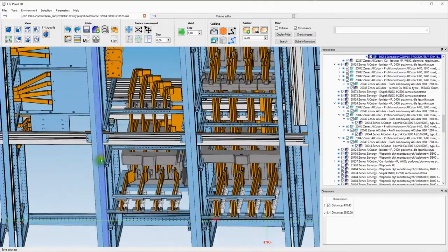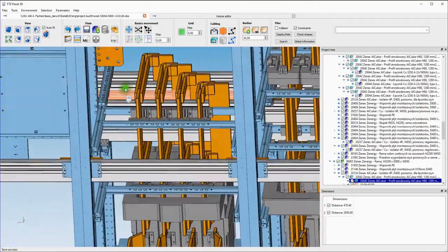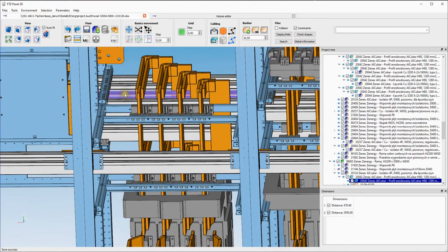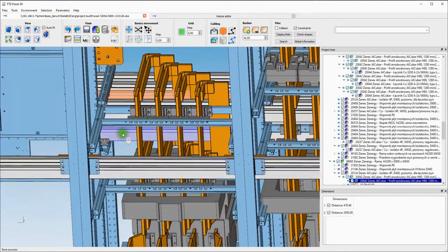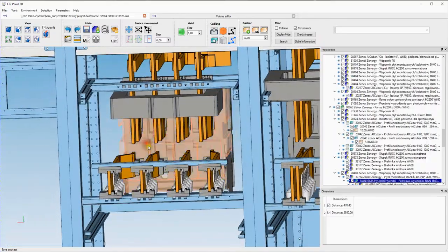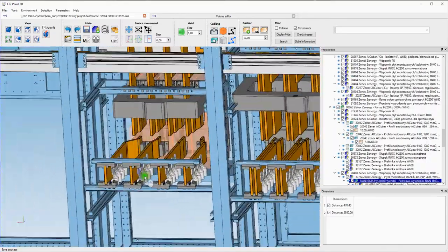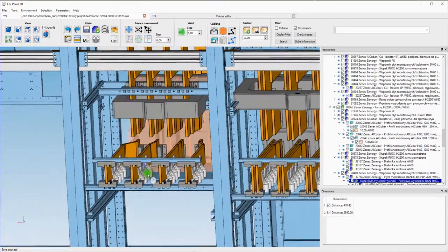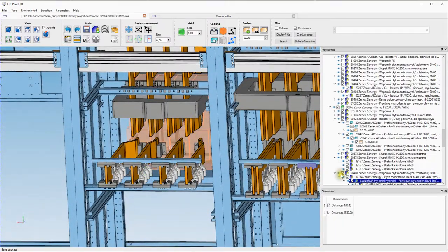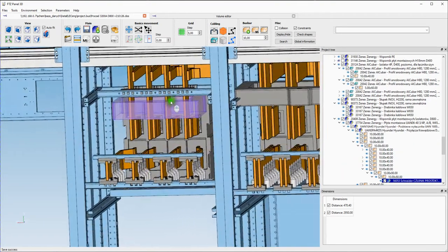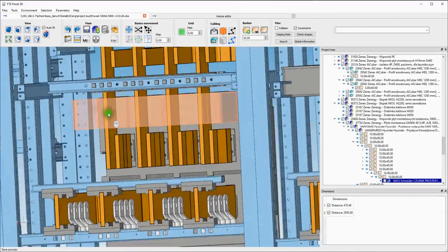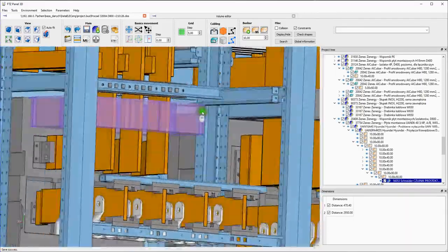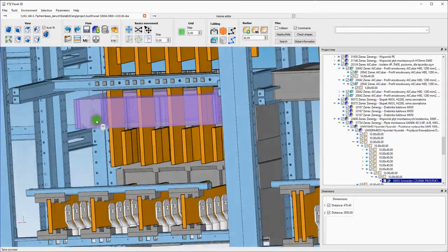Later at the outgoing of the main 3200 bus duct, we have one breaker 2500 with outgoing cables. 2500? No, sorry. The outgoing here is 1500, also with the earth leakage current transformer. So here you can see that the current transformer fits very nicely and we have no problem here.